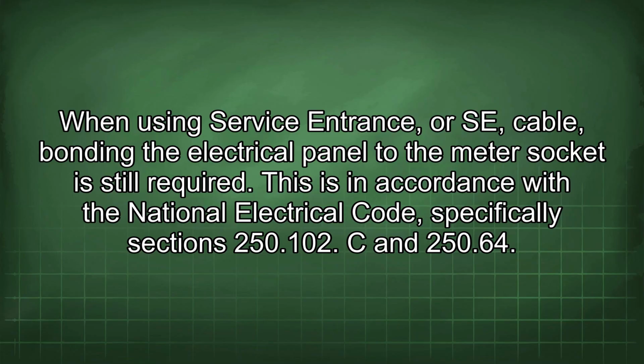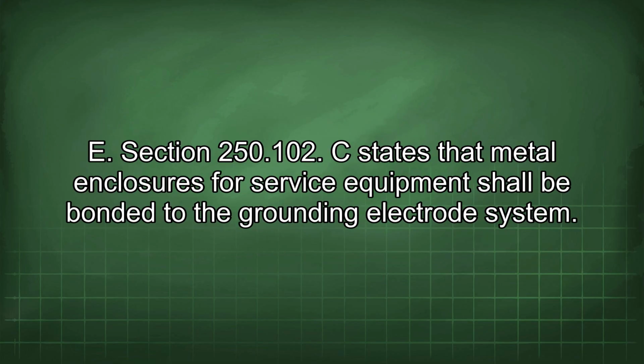When using service entrance or SE cable, bonding the electrical panel to the meter socket is still required. This is in accordance with the National Electrical Code, specifically sections 250.102(C) and 250.64. Section 250.102(C) states that metal enclosures for service equipment shall be bonded to the grounding electrode system.